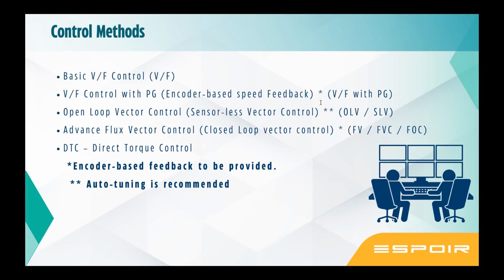There are different algorithms to use for different applications. You can check. The basic V by F control is one. Now, V by F control is just by an algorithm. It doesn't have feedback. So the drive works blindly and sets its output. Now, what if you give feedback to the system? It can improve certain performance. I will tell you what the performance differences between the different control methods are in the next slide. I'll just brief you on what V by F is. Next is V by F control with encoder feedback from the motor. The third one is open loop vector control, or sensorless vector control, which means you try to understand the motor model in a much better way by doing an auto tuning.